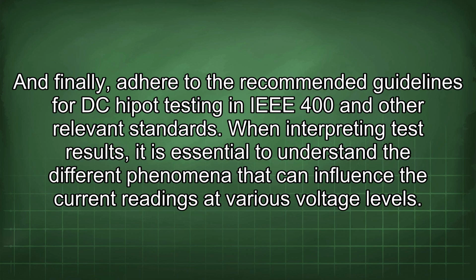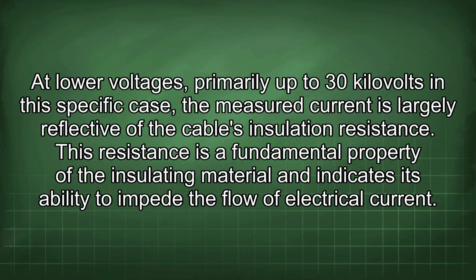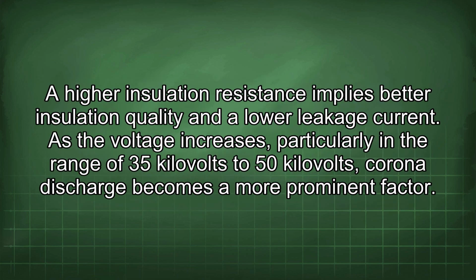When interpreting test results, it is essential to understand the different phenomena that can influence the current readings at various voltage levels. At lower voltages, primarily up to 30 kilovolts in this specific case, the measured current is largely reflective of the cable's insulation resistance. This resistance is a fundamental property of the insulating material and indicates its ability to impede the flow of electrical current. A higher insulation resistance implies better insulation quality and a lower leakage current.